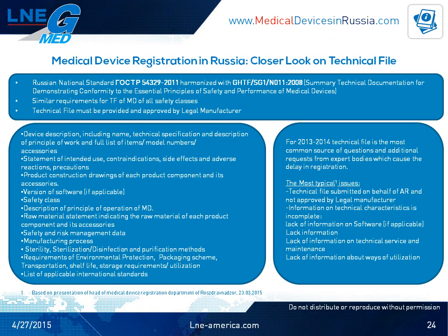Technical file must contain information about short description of manufacturing process, statement about sterility and description of sterilization and disinfection and purification methods and its validation, requirements on environmental protection as well as a description of packaging scheme, requirements on transportation, information about shelf life, storage requirements, and requirements for utilization. It's very important to mention the version of software if this information is applicable. You should provide as well the list of applicable international standards for a medical device in the technical file.